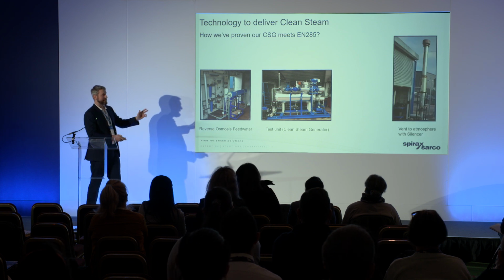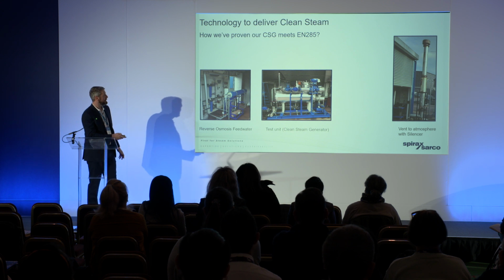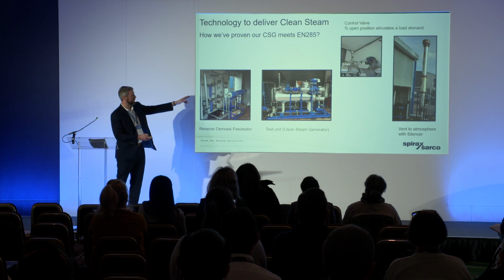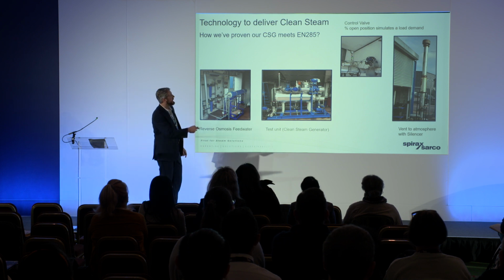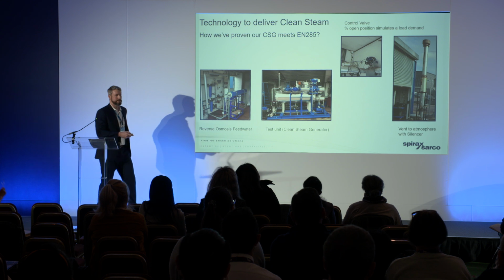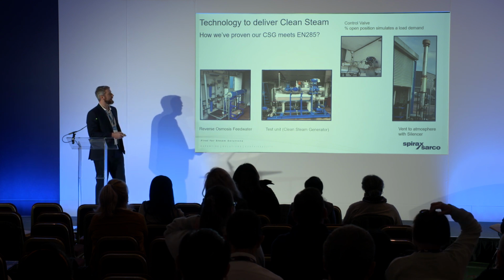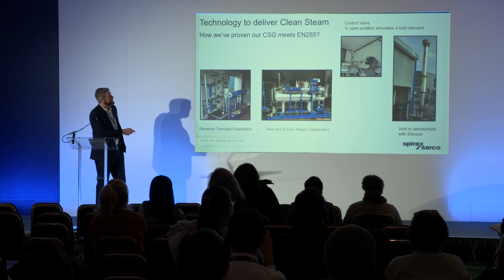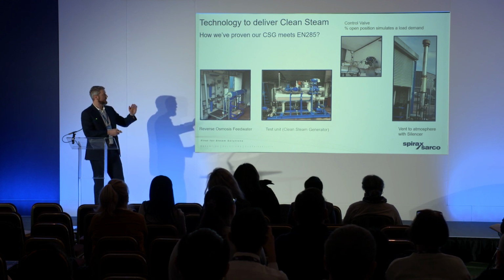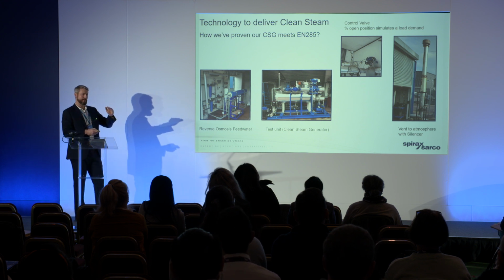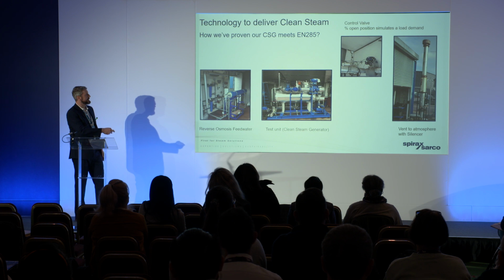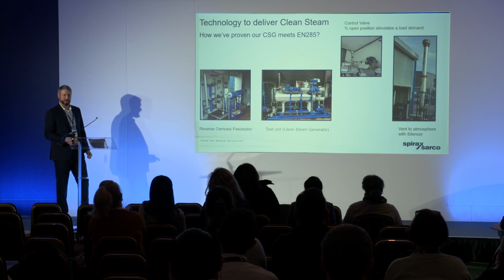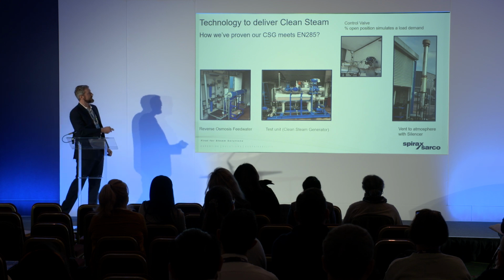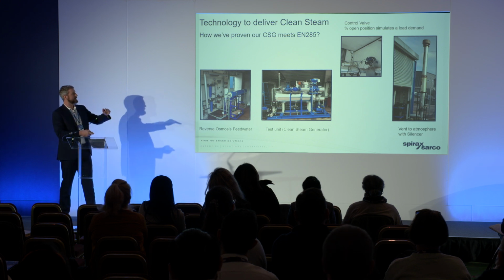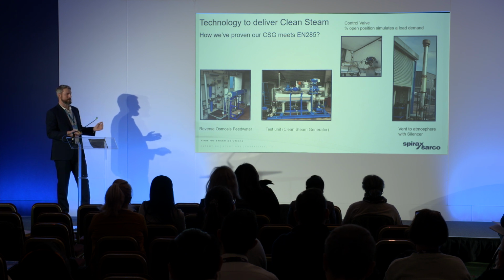Unfortunately, we had to vent that steam to atmosphere. But on the outlet pipework, which would otherwise go to the sterilizers, we had the ability to continuously monitor the steam dryness, NCGs and superheat. And here you can see a control valve. Depending on its opening position, this control valve could create a demand on the clean steam generator, which would simulate your sterilizers consuming that steam. So with a steam meter and these different control valve open positions, we could model different load scenarios on our clean steam generator.